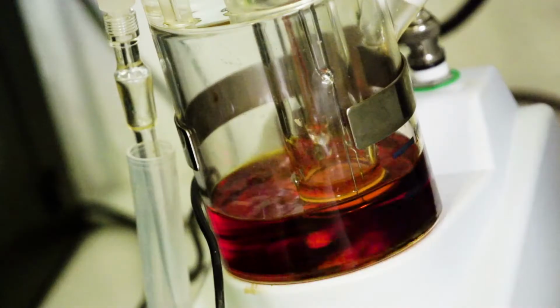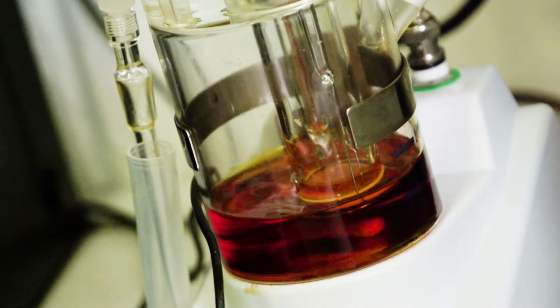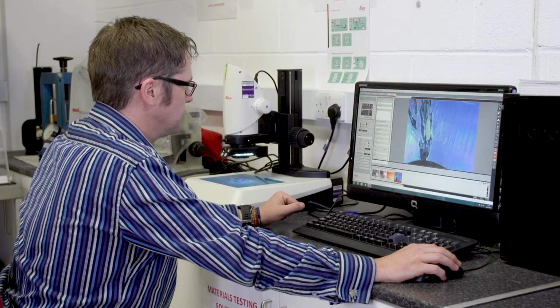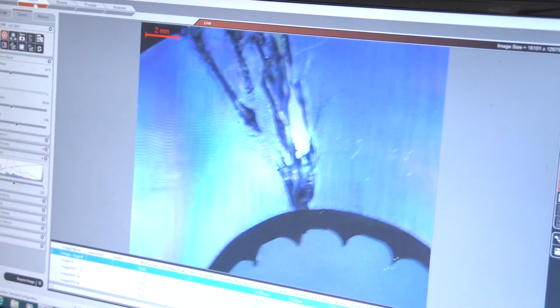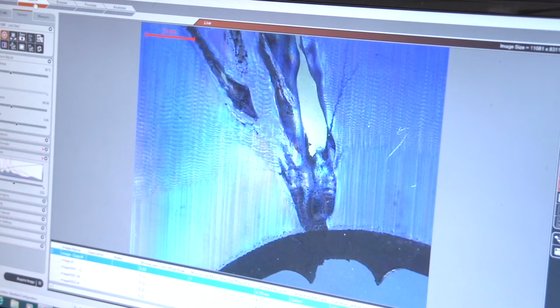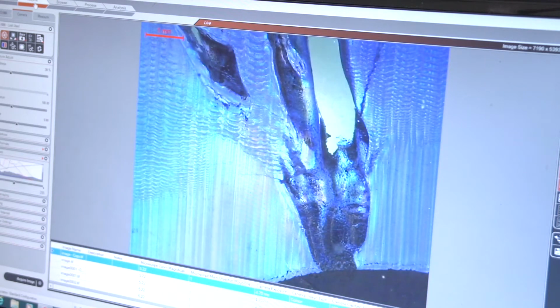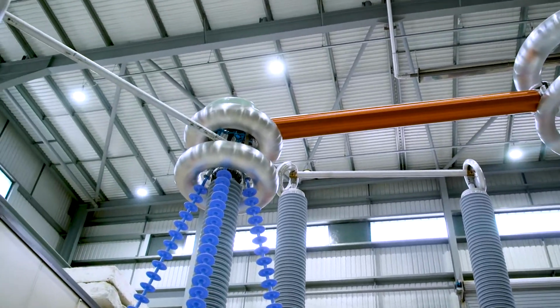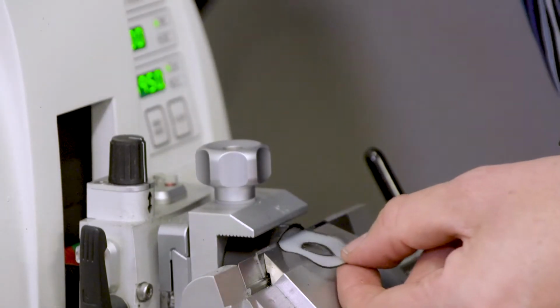We do a series of chemical steps, and that allows me to see what is actually going on within the insulation and how that cable has performed over time, and hopefully how long that cable will be able to last in the field. The unique aspect of this facility is that we can do the full range of electrical tests and material tests at the same time, and there aren't many facilities that can do that.